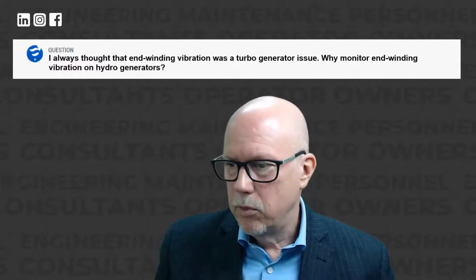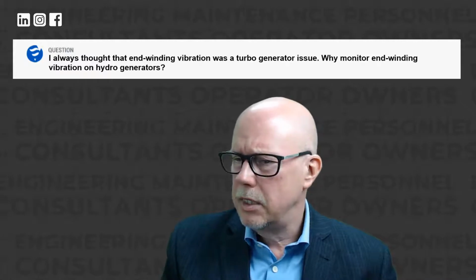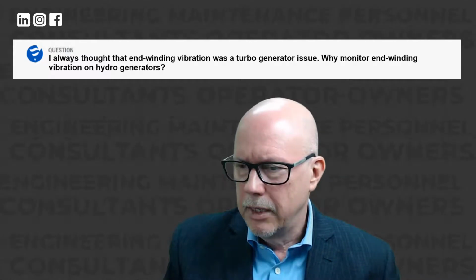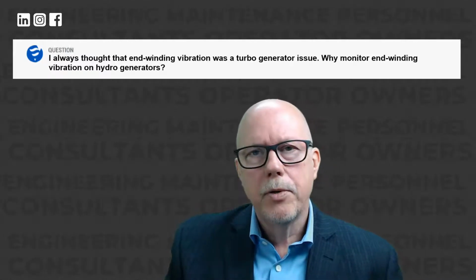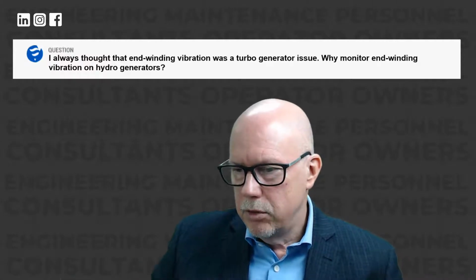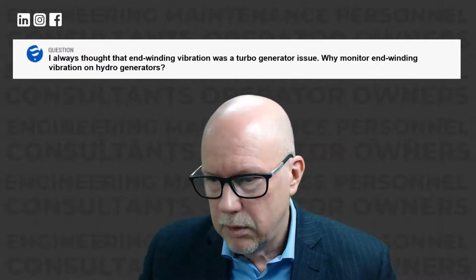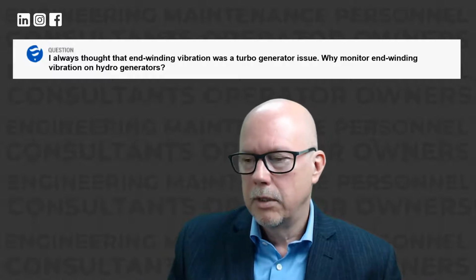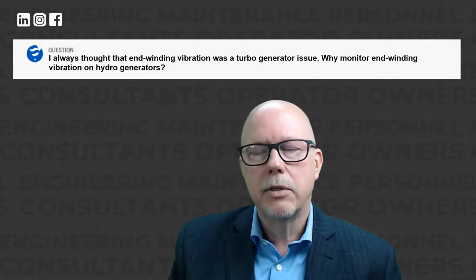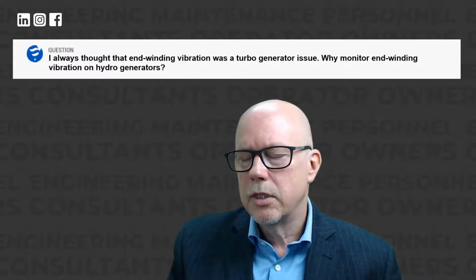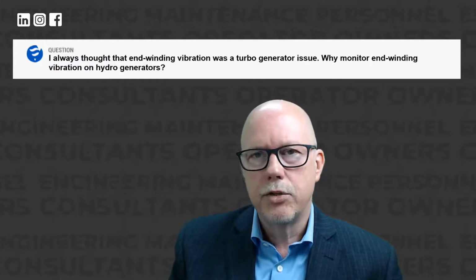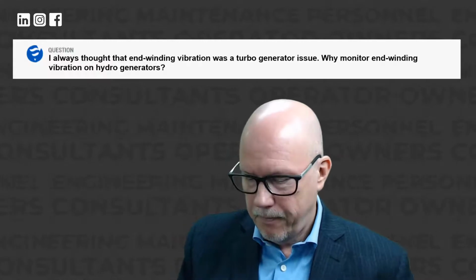And the paper was published quite a few years ago at the CIGRE conference, if I remember correctly. So it is more popular on turbo generators because of the issue. They have more issues, so using fiber optic is more common. But there are quite a few hydro units and quite a few mills, ball mills and SAG mills, in the mining industry that use this type of technology to try to avoid major failures at the end winding level.